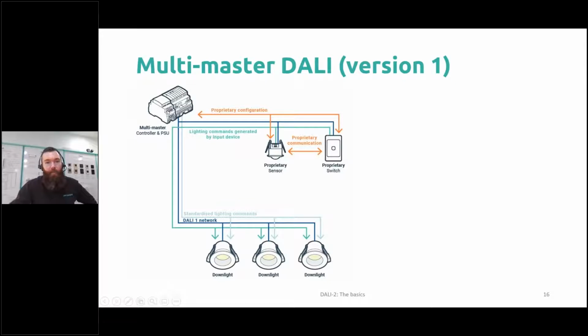We then moved to the idea of multi-master. This gave a lot of advantages because now we had the same network—as you moved into one particular room, you could have your switches, your sensors, your lights, your emergency, all on that network, drastically cutting down the amount of wiring and the amount of time you had to spend commissioning those systems. But we still had the issue that the actual sensors had to be very complicated devices.